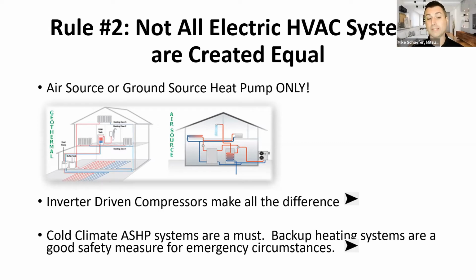What an inverter compressor does is it starts up fast to drop that space temperature, or in heating, raise that space temperature. Then once it hits the space temperature, it just modulates down. So it goes where you want to go, gives you as much heating or cooling as you need, and then it just cruises to maintain. Think of it as highway miles in your car versus city miles. A single-stage compressor is start and stop, and an inverter-driven compressor is cruise control.